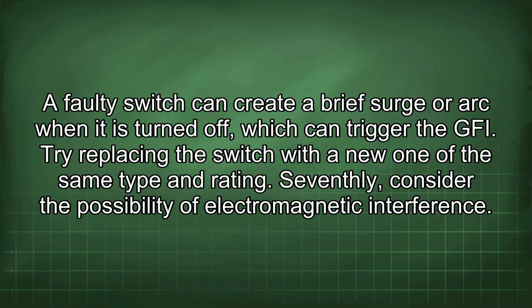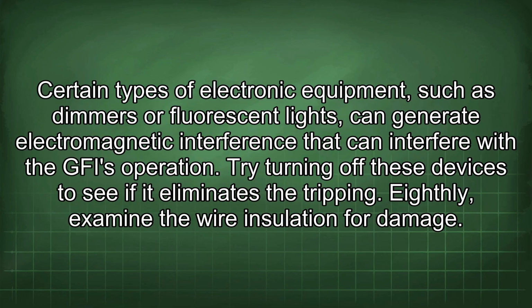Seventhly, consider the possibility of electromagnetic interference. Certain types of electronic equipment, such as dimmers or fluorescent lights, can generate electromagnetic interference that can interfere with the GFI operation. Try turning off these devices to see if it eliminates the tripping.